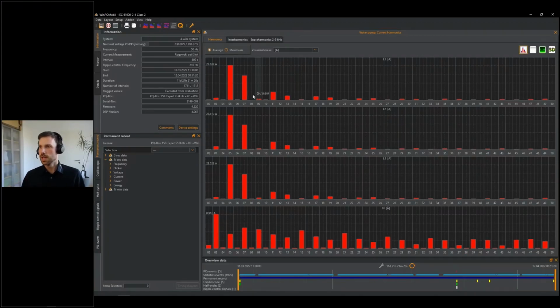First of all, I see there are high emissions on the 5th and 7th order, 11th and 13th order, and so on and so on. This is very typical for a B6 rectifier, a classic rectifier. But these values are in amps. I do not see any limit lines. Well, that's because the visualization is in amps.